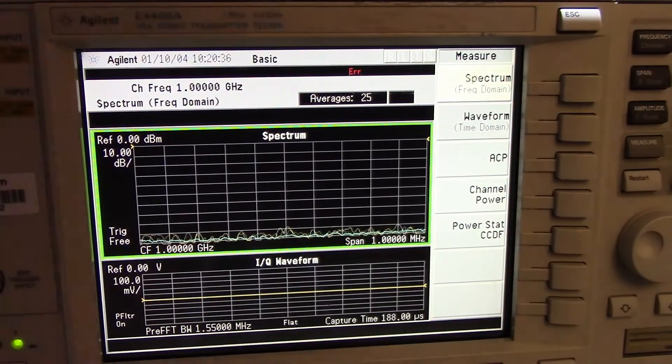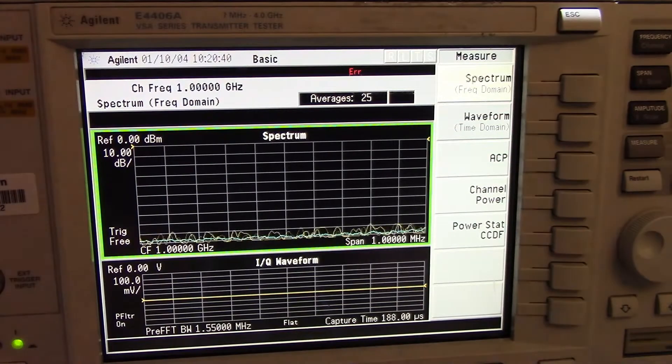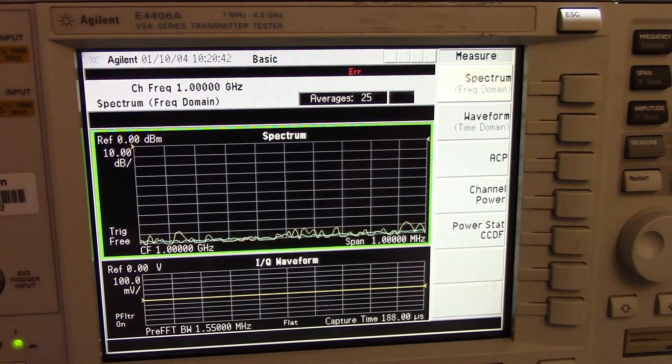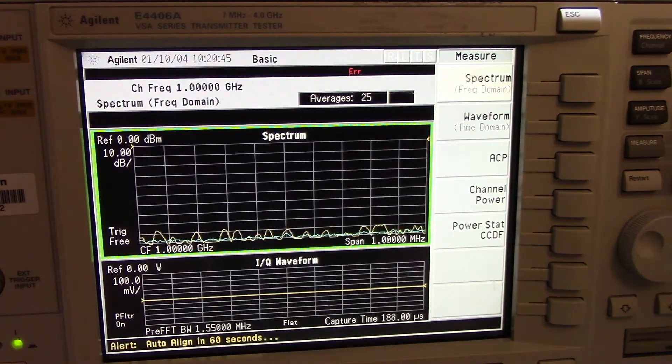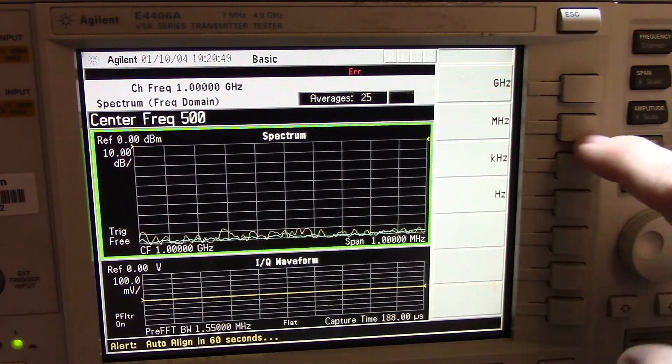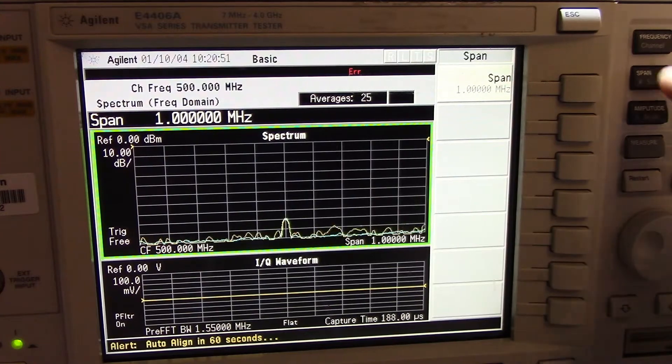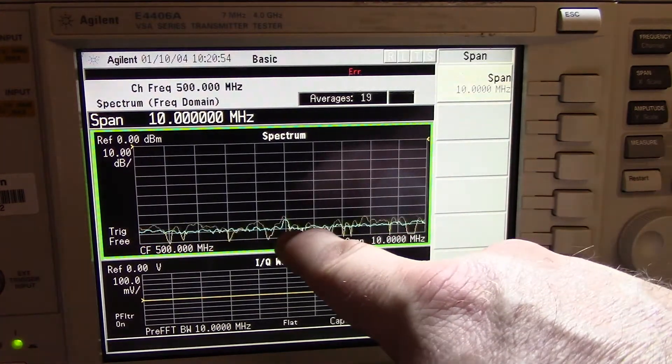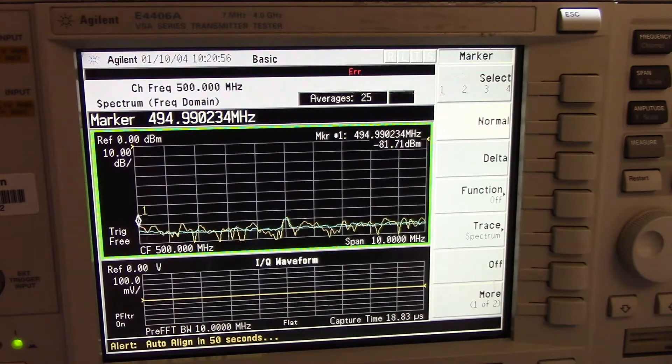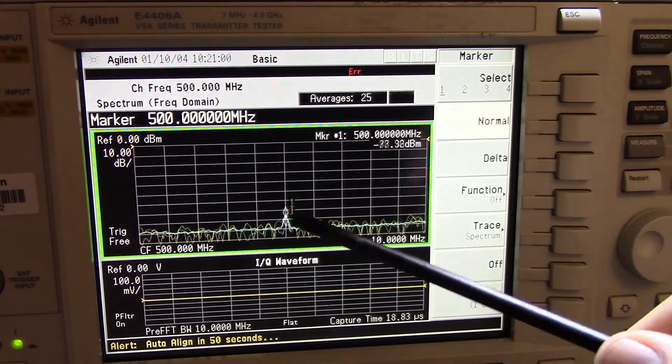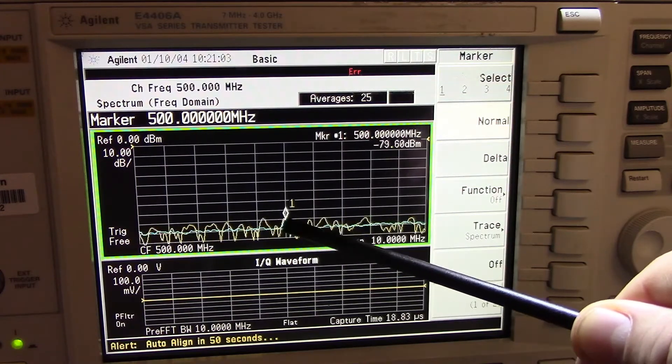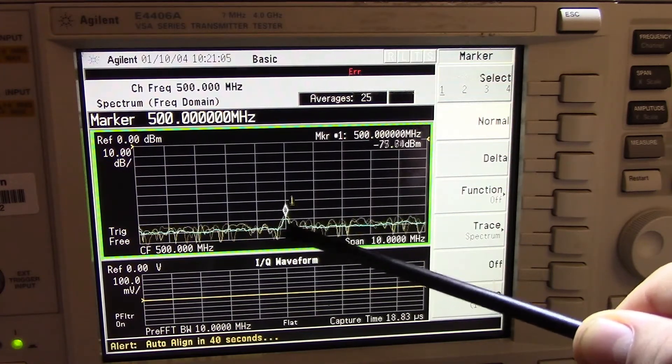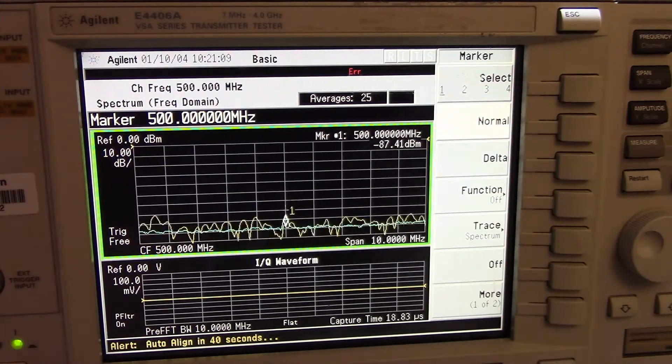Now what I have here is I have a 500 MHz signal coming in. Let's set that 500 MHz and we'll set the span to be 10 MHz. Then if I put a marker in here at 500 MHz you can see that I have a signal in there. That blue line is the average and so you can see there is a signal there above the noise, but it's very low, it's like 60-70 dB low right now.